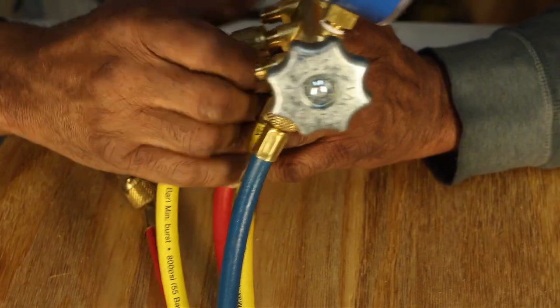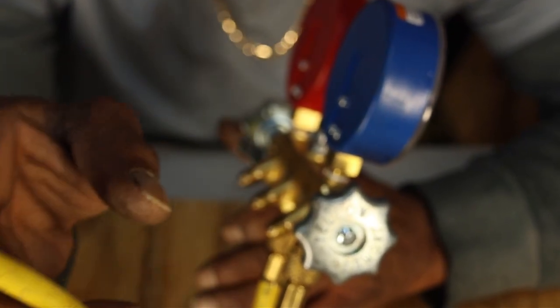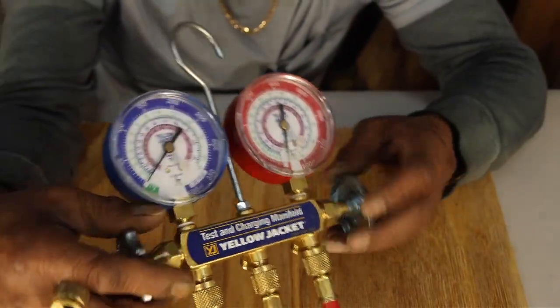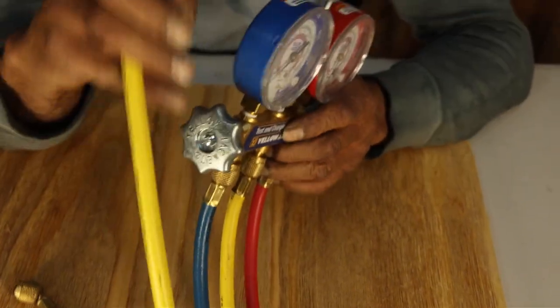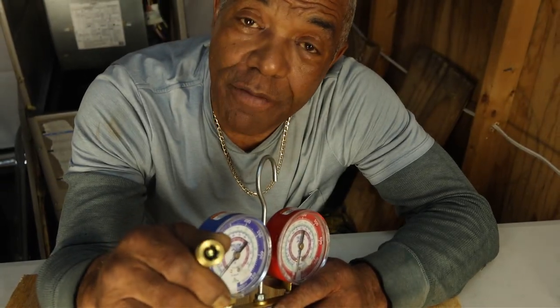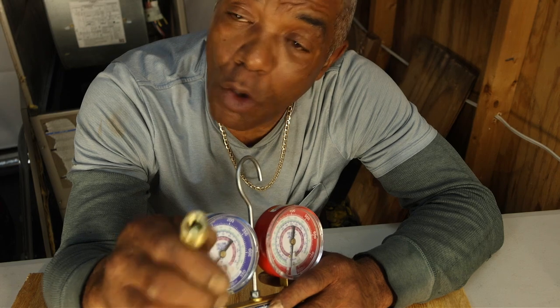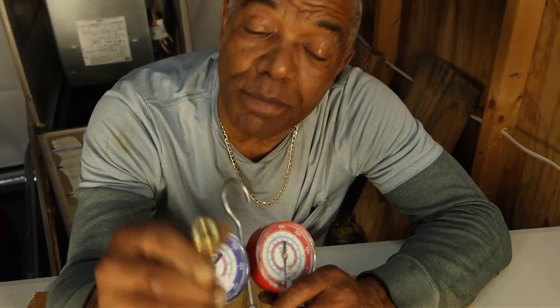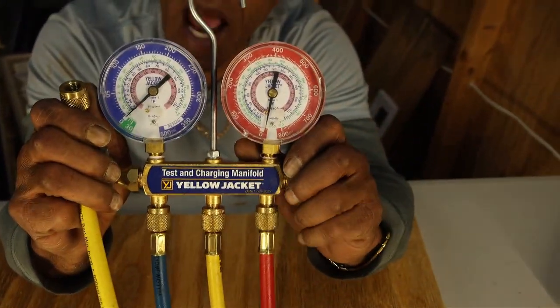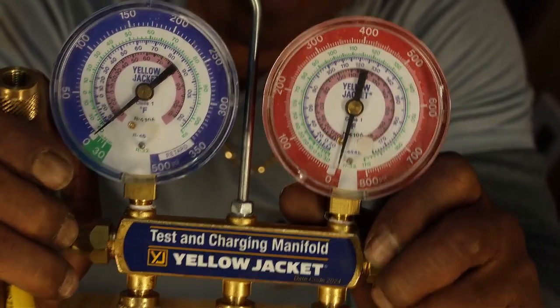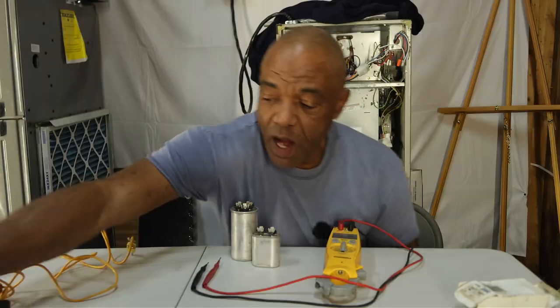Now, the yellow line, I would use that either if I were charging the system with Freon, I would hook the yellow line to my actual Freon tank and hook the red and the blue to the system, and then I can open the different sides and let the Freon go in. Or I can use this as a vacuum. Whenever you open a system up, you must vacuum it down, or I may need to recover the Freon out of the system. But we're going to talk about all of that in the class. I'm going to show you the recovery method. I'm going to show you the charging. But I do want you guys to get a set of gauges for the class that you have them. Let's move along.